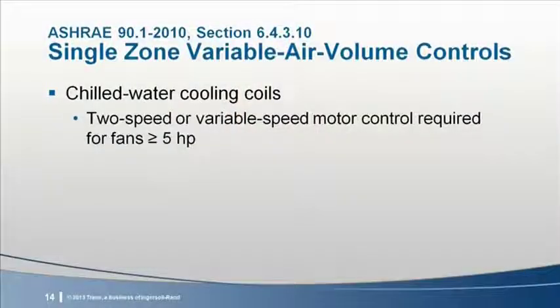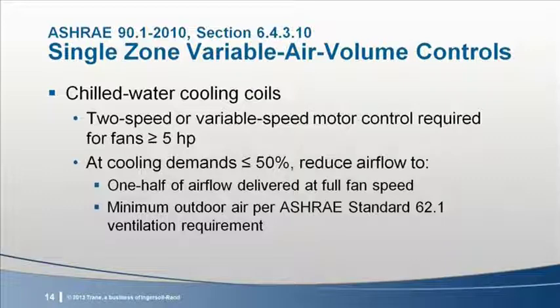2-speed fan control would be sufficient to meet variable airflow requirements, and the accompanying user's manual clarifies that ECM motors can be used too. The supply fan controls must be able to reduce airflow to at least 1/2 of the airflow delivered at full speed, or down to the volume of outdoor air required to meet ASHRAE Standard 62.1, if that's larger than the 50% threshold. This is meant to prevent the system from underventilating.